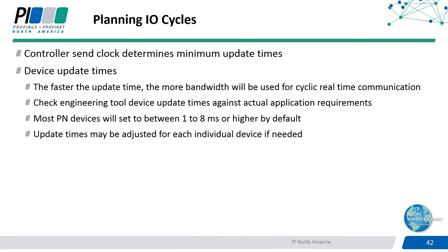In addition, each I/O device has a minimum time possible that comes in with the vendor GSD file, the device description file that you get with the device. They're going to have a minimum update time in there. Now, when you're setting up these devices in the engineering tool, typically the engineering tool is going to pick the minimum times automatically. But we find sometimes this may not always be the best idea or optimal for your network.